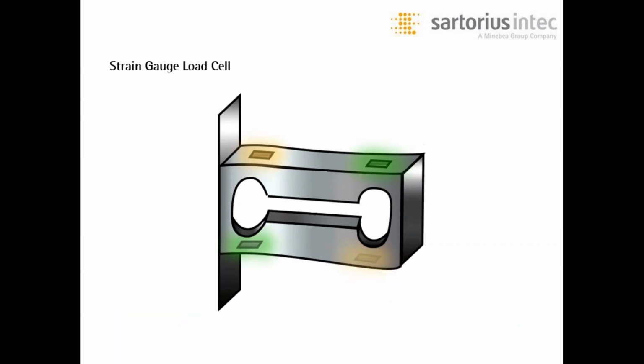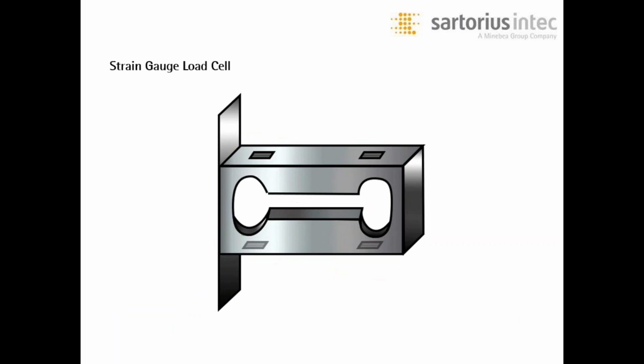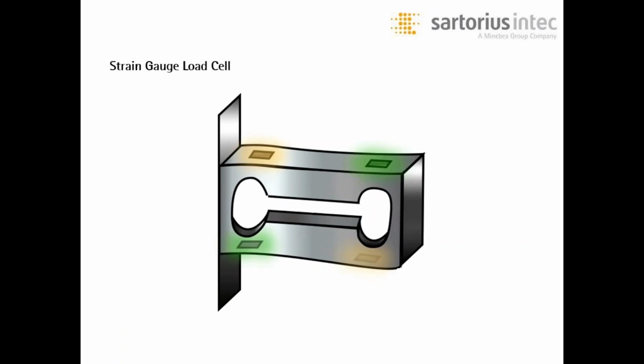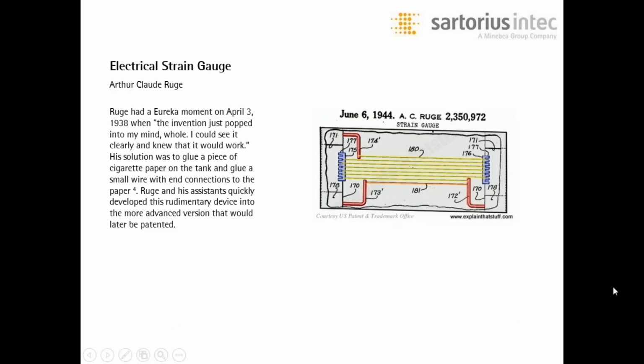Let's start a discussion with the most common weighing element, the strain gauge load cell. This is the most common load cell used in the weighing industry. It can be found in bench platforms, floor scales, and in some cases, tank and hopper systems. The most common electrical strain gauges are thin, rectangular-shaped strips of foil with maze-like wiring patterns on them leading to a couple of electrical cables.